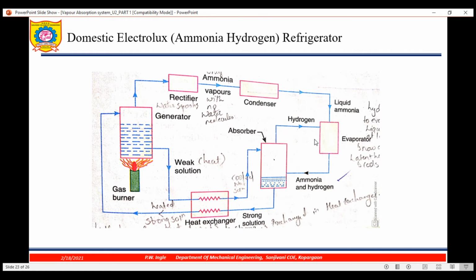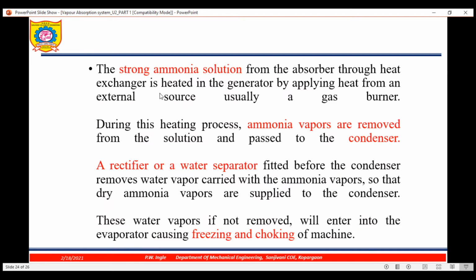Now I will read step by step. The strong ammonia solution from the absorber through the heat exchanger is heated in the generator by applying heat from an external source, usually a gas burner. During this process, ammonia vapors are removed from the solution and passed to the condenser. The rectifier or water separator fitted before the condenser removes the water vapor carried with the ammonia vapor, so that dry ammonia vapor is supplied to the condenser.